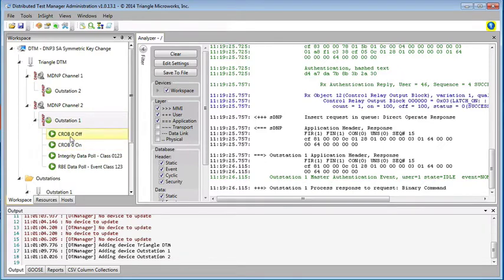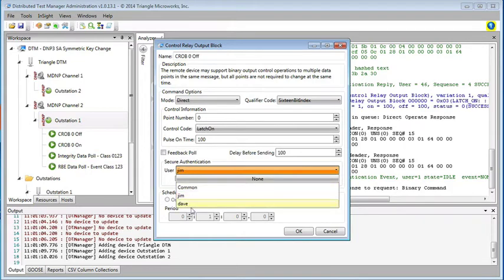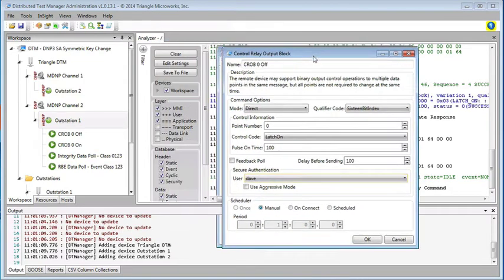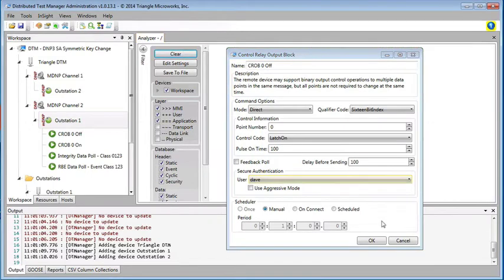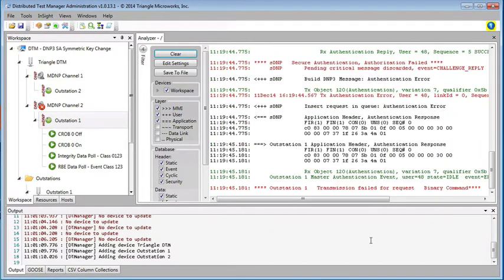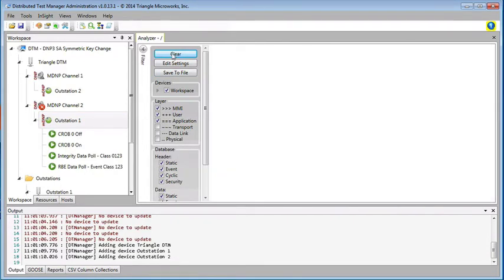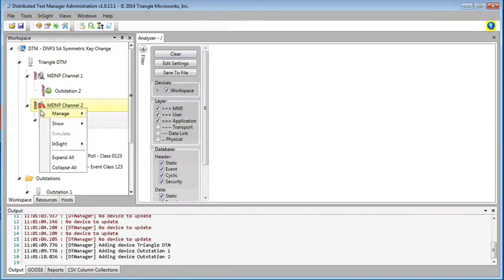Now let's send another CROB command, but this time let's send it by Dave. Remember Dave's a viewer. So let me clear the log, and then we'll send the message from Dave, or try to send the message from Dave. We see that the command fails because of the challenge reply, because Dave is a viewer and not allowed to send controls. Notice we have an error message now telling us that the CROB command failed.